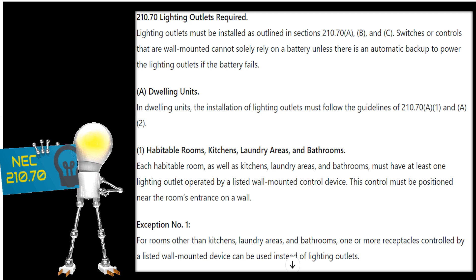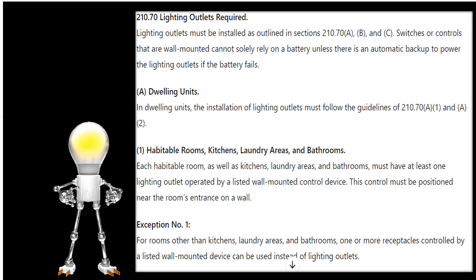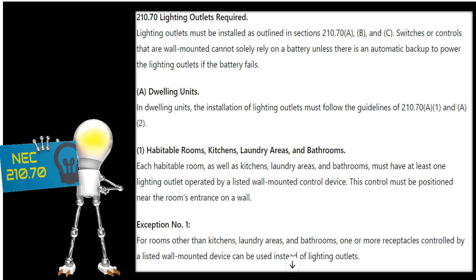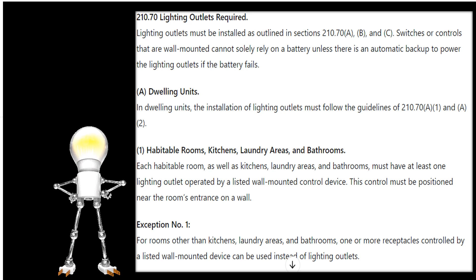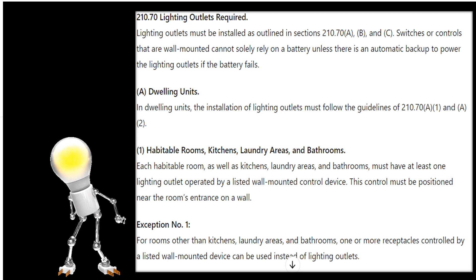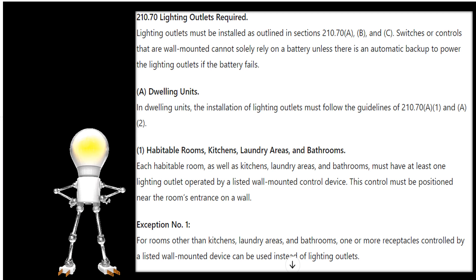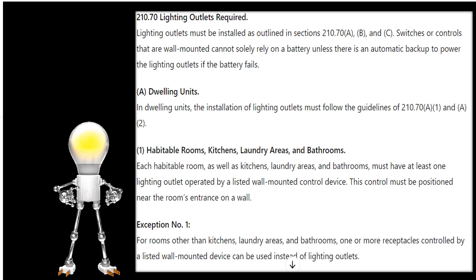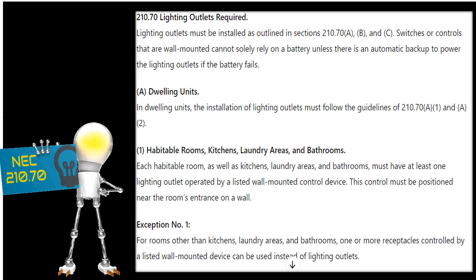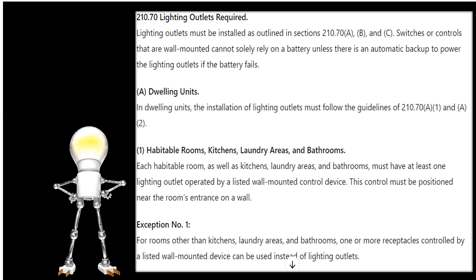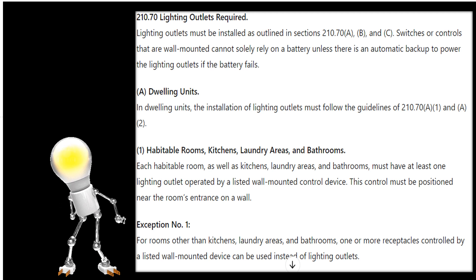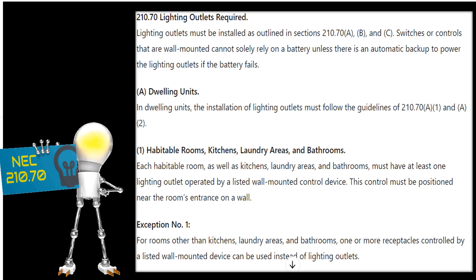Let's look at Exception 1. For rooms other than kitchens, laundry areas, and bathrooms, one or more receptacles controlled by a listed wall-mounted control device can be used instead of lighting outlets. So in any of the other rooms listed in Part 1, you can use a receptacle controlled by a general snap switch or a listed wall-mounted control device — whatever that looks like now or in the future.